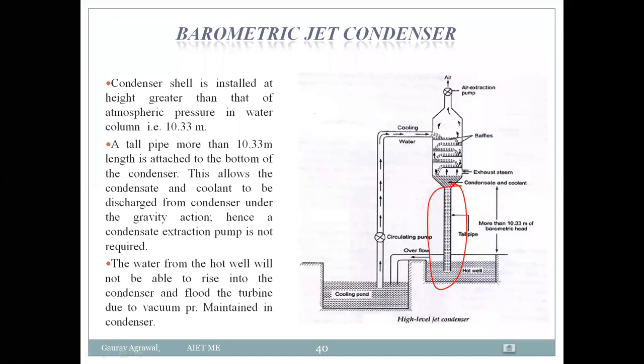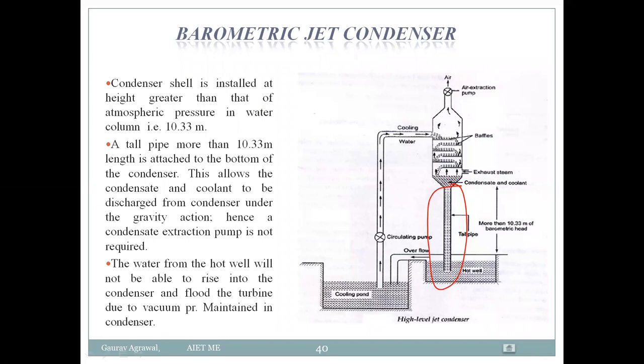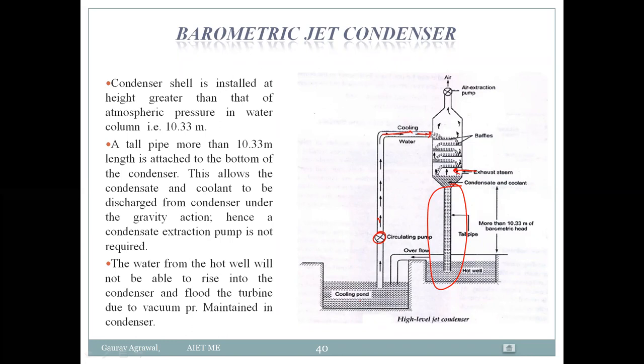The atmospheric pressure gap corresponds to approximately 10.33 meters of water column. This allows the condensate and coolant to be discharged from the condenser under gravity action, so a condensate extraction pump is not required here. The remaining structure includes a circulating pump and a cooling pond.